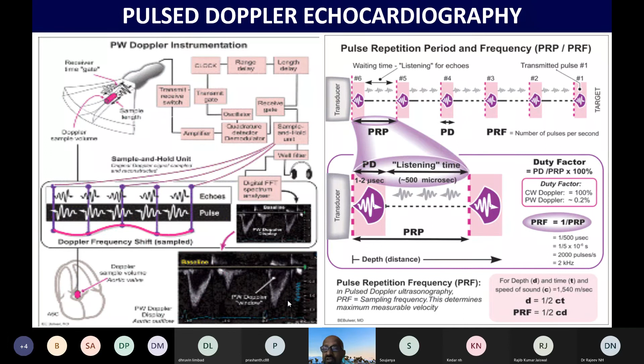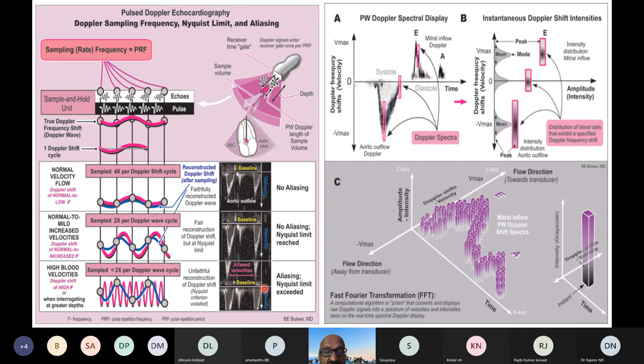And to avoid this, you have to ensure that the pulse repetition frequency, the sampling, matches the Nyquist limit. So here you are seeing normal velocity flow using pulse wave Doppler, and there is a faithful reconstruction of the Doppler wave. But as the velocity increases and the Nyquist limit is exceeded, the waveform which is going towards the bottom of the screen actually comes onto the top of the screen, and this leads to errors in interpretation of the velocity. Hence, if the velocity is higher, we must go for continuous wave Doppler.